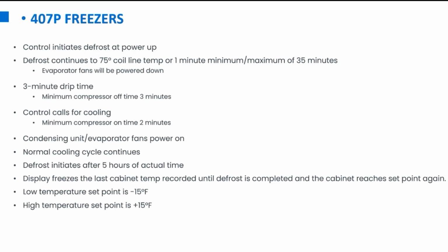So once that defrost is over, and whether it terminates by time or temperature, you'll have a 3-minute drip time where essentially nothing will be happening there. The unit's just going to be allowing that coil to drip with the water that's melted off of it. From there, there'll be a call for cooling. Condensing unit kicks in, evaporator fan kicks in, and the unit begins cooling.